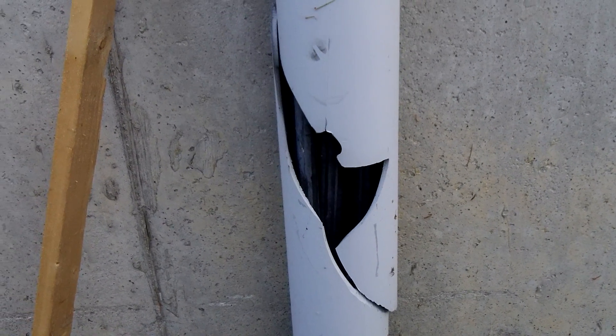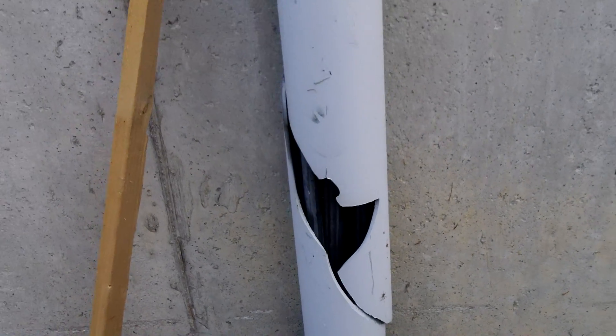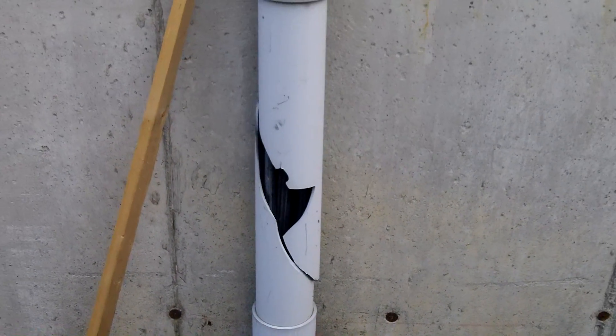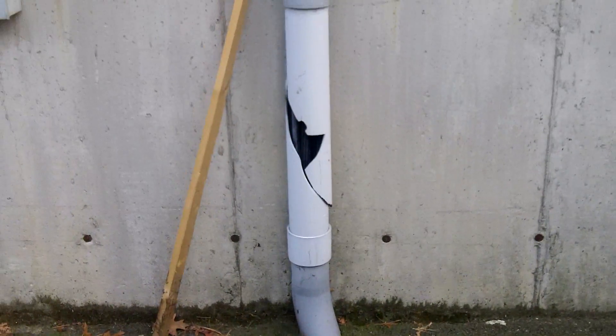This could definitely be a dangerous situation. Water could get into that pipe, and who knows if the wires themselves may be damaged at this point.